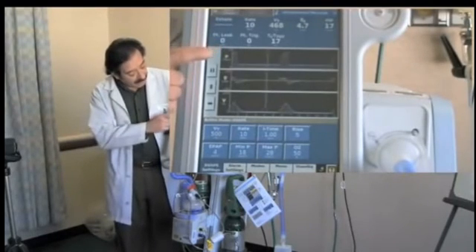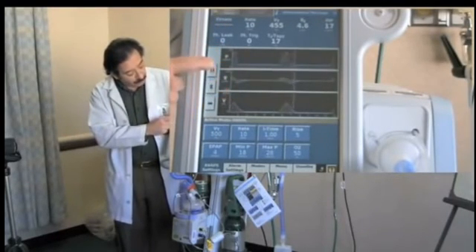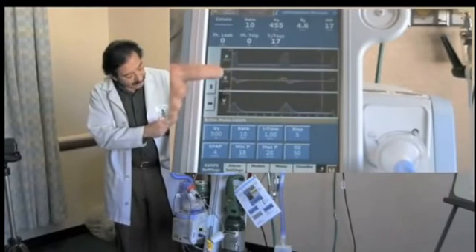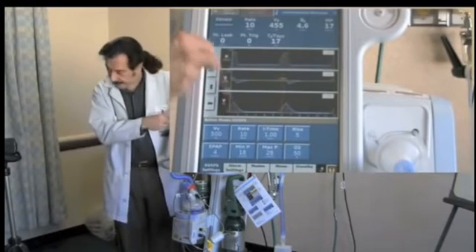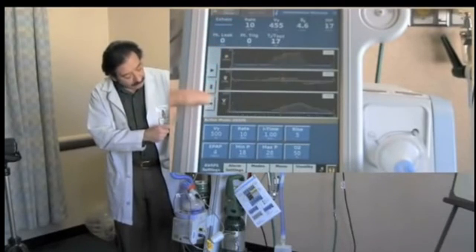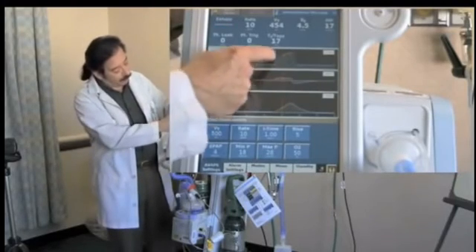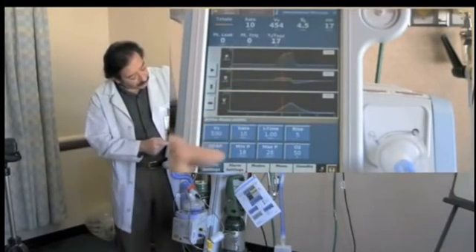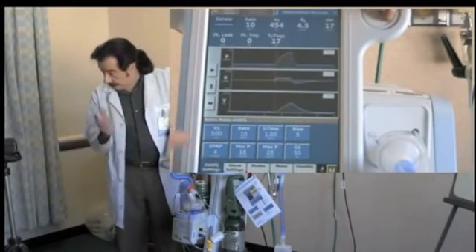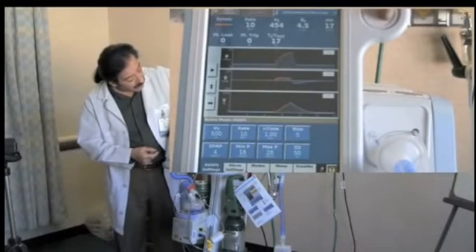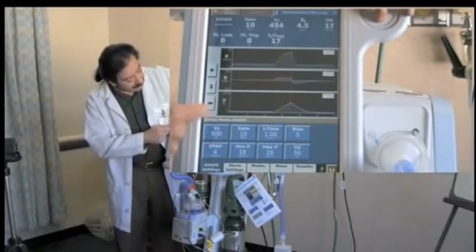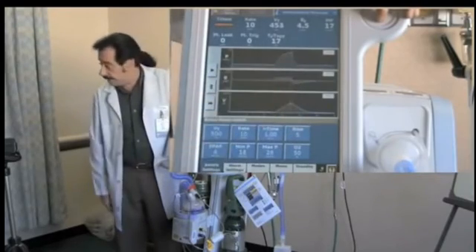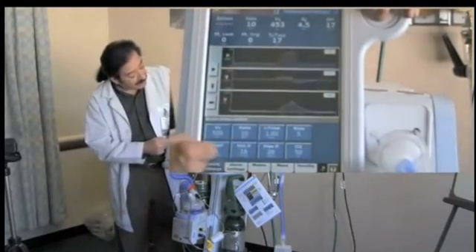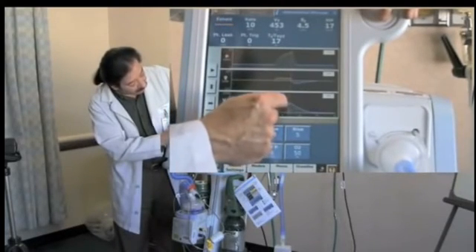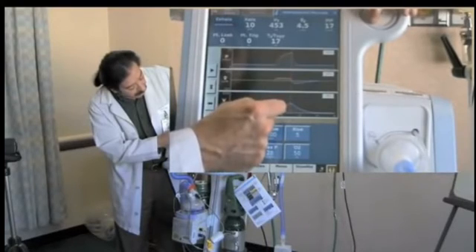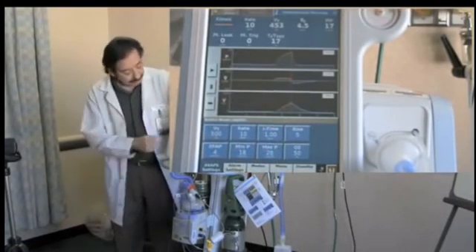Okay. You have pressure, flow, and volume. The waveforms can be frozen for analysis. You can change the y-axis, or the amplitude of the waveforms, or the time frame of the waveforms. Okay? Now, once the waveform is frozen, you can use the scroll wheel to move this red cursor bar to get various information about that breath that you froze. Okay, so here I know that the peak flow attained on that breath was 22.8 liters a minute at 16.8 centimeters of water pressure, peak pressure, and a peak volume of 492 cc's. Okay?